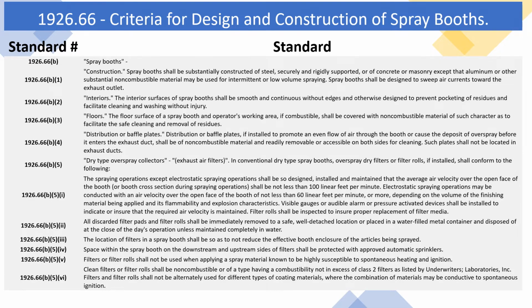1926.66 B. Spray booths. 1926.66 B.1. Construction. Spray booths shall be substantially constructed of steel, securely and rigidly supported, or of concrete or masonry, except that aluminum or other substantial non-combustible material may be used for intermittent or low-volume spraying. Spray booths shall be designed to sweep air currents toward the exhaust outlet. 1926.66 B.2. Interiors. The interior surfaces of spray booths shall be smooth and continuous without edges and otherwise designed to prevent pocketing of residues and facilitate cleaning and washing without injury. 1926.66 B.3. Floors. The floor surface of a spray booth and operator's working area, if combustible, shall be covered with non-combustible material of such character as to facilitate the safe cleaning and removal of residues.